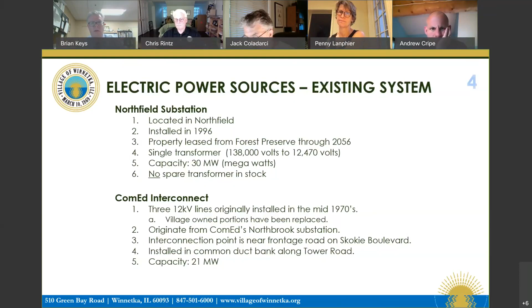The remaining third source of power is the electric plant. Just for a quick refresher, down there are two diesel units that were purchased in 1978. They're nominally rated 2400 kW. They can be put online in 90 to 120 minutes, faster if staff is there. But if it's one person on a weekend, it's going to take longer than on a weekday when there are multiple people in the building. We get annual capacity credits from IMEA for our generating units, meeting certain test outputs, and for the diesels we get $184,320 on an annual basis.